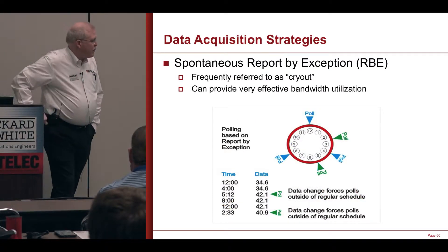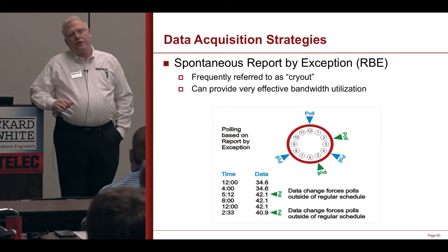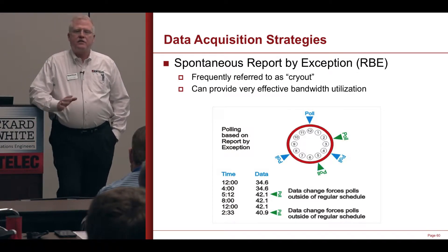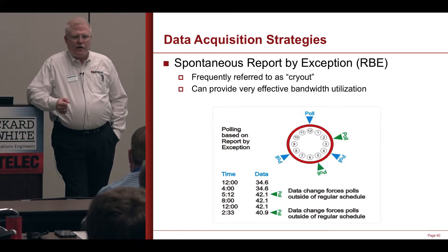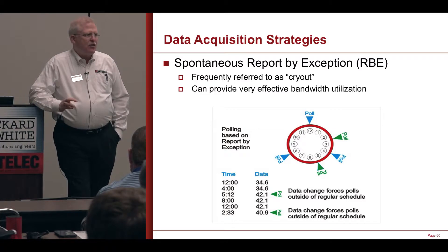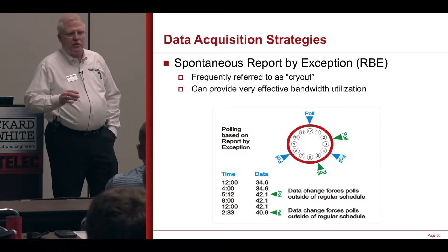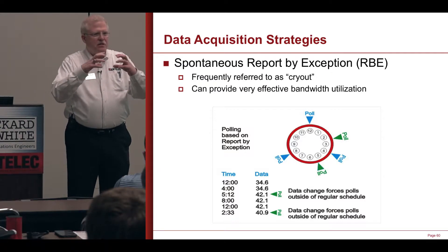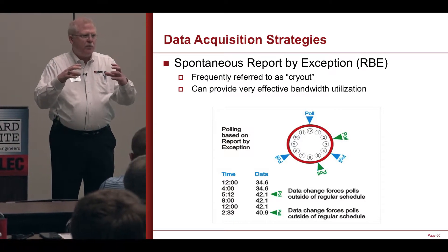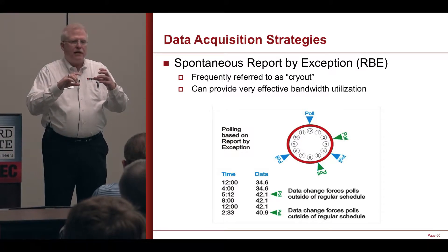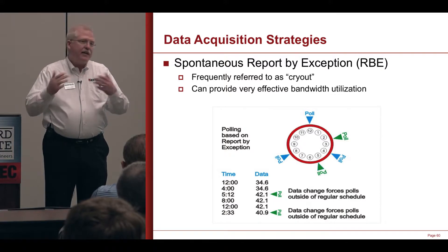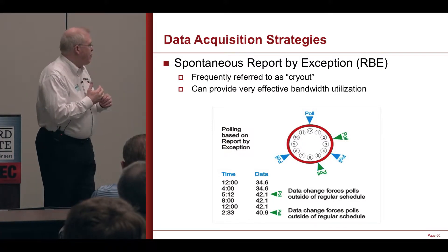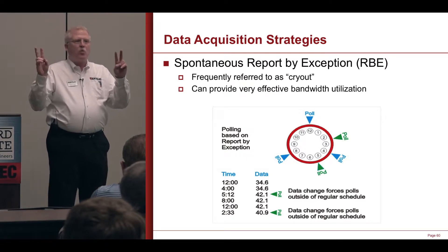There's also what's called report by exception. Modbus is a simple poll response protocol — when I issue a poll, I read a register and report back the value in that register, and that's all it does. DNP3 is a report by exception protocol, so it actually builds up a cache of all the data that changed since the last time you polled, provided it's outside of a dead band, and when I hit it, I get all those data values. If there were no changes, I don't get any data values. That's called a report by exception.